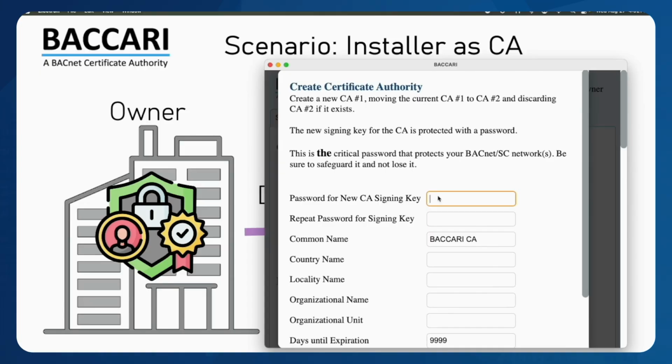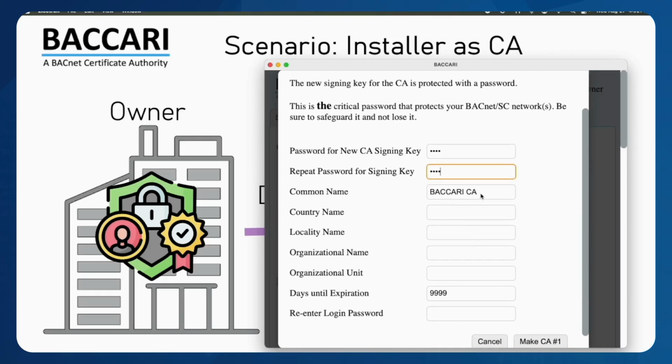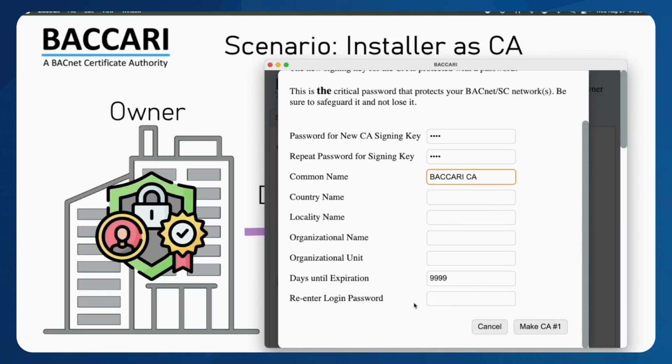Now, this is the most important part. This is the password for this certificate signing key that is used for signing certificates for your BACnet SC network. So don't lose this password. We will go ahead and create that. And you can call it whatever you want. We'll just leave it as BACCARI CA.